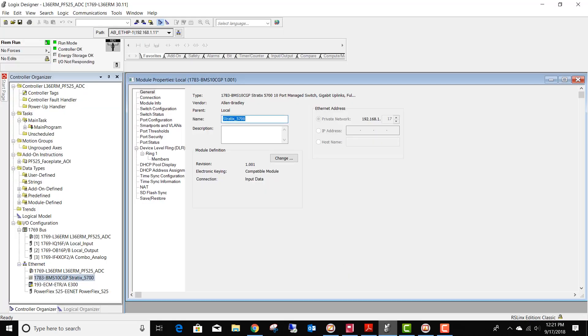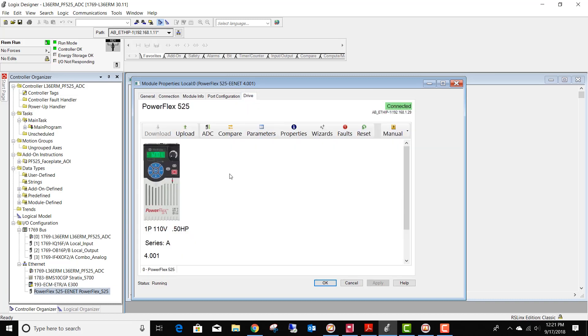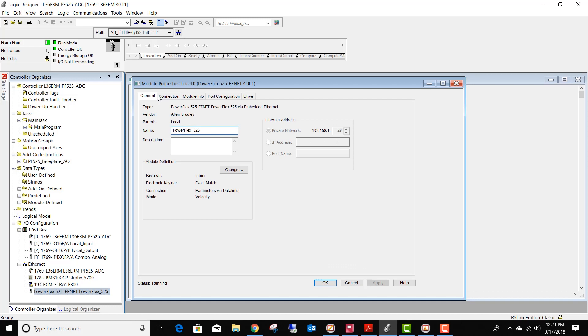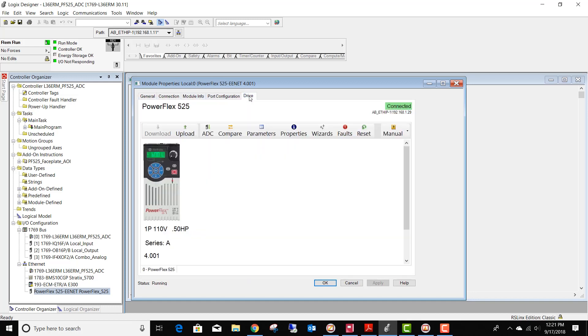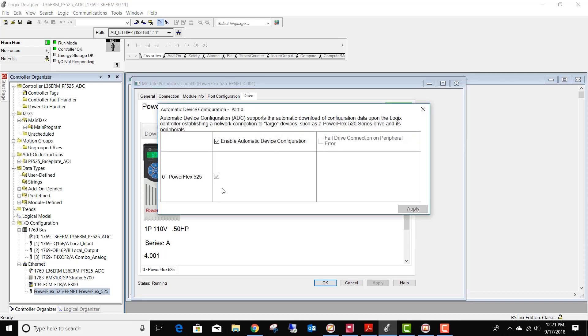Now we open up Logix Designer because we're through with the switch. In Logix Designer, we go down to our ADC-enabled device, which happens to be our PowerFlex 525 drive. We click on the Drive tab — you have across the top: General, Connection, Module Information, and Port Configuration. To set up ADC, you click on the ADC button. And when you do that, you can see how difficult this is going to be to set up — you simply check the box, and you have just now configured ADC.